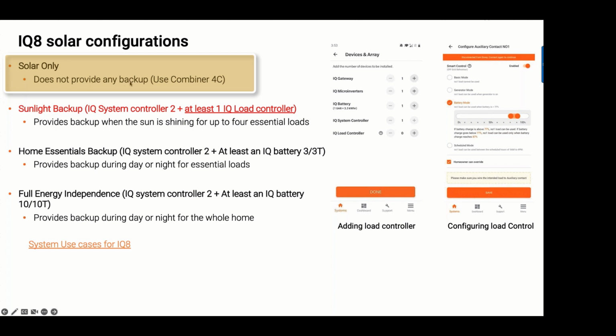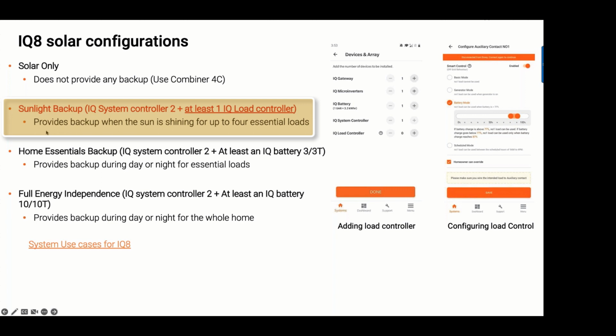In that configuration, there's no backup power. It's just solar for grid tied. The second configuration is called sunlight backup. Sunlight backup is now taking those inverters and saying, this is not just a grid tied system. These inverters can actually form a grid if the utility goes away. So that means that customers that have sunlight backup, if the utility fails, if they've got sun on solar panels, you're going to get power in the house. That's called sunlight backup. That's using IQ8s to form a grid and create backup power.